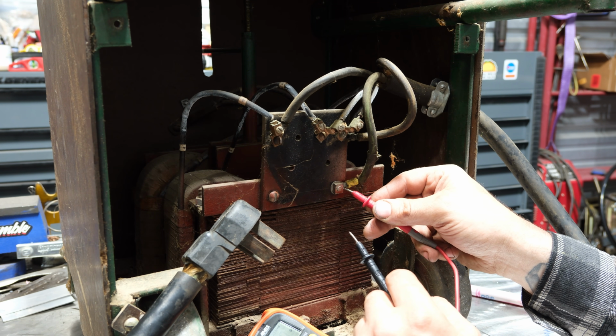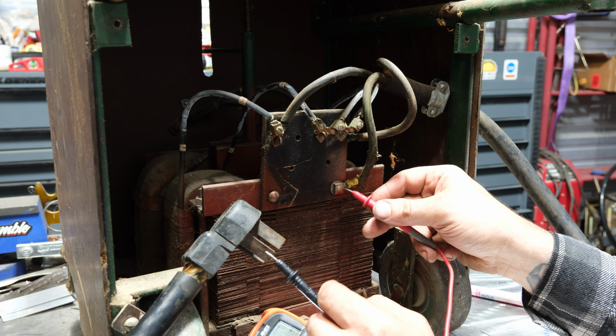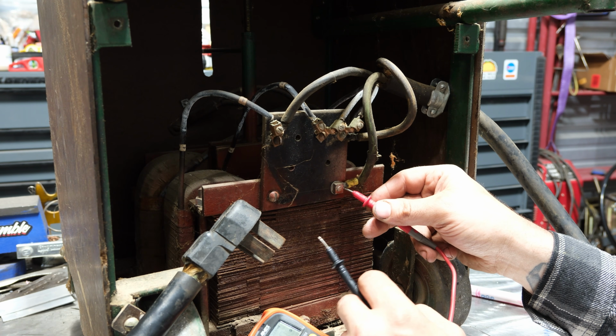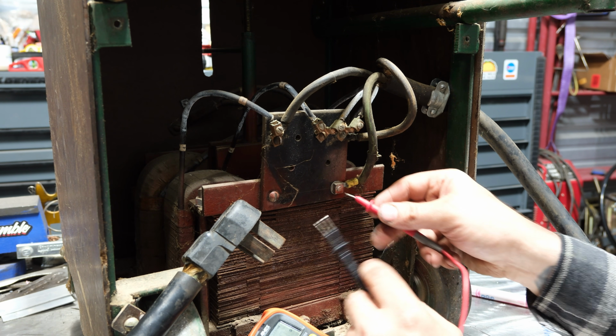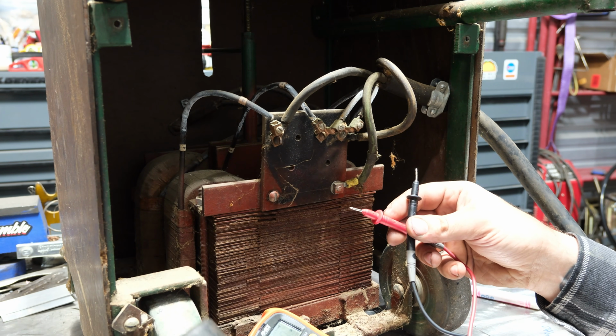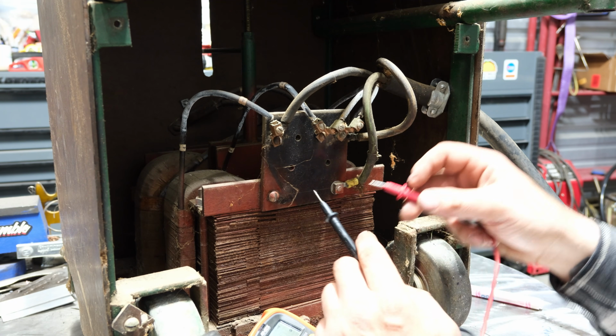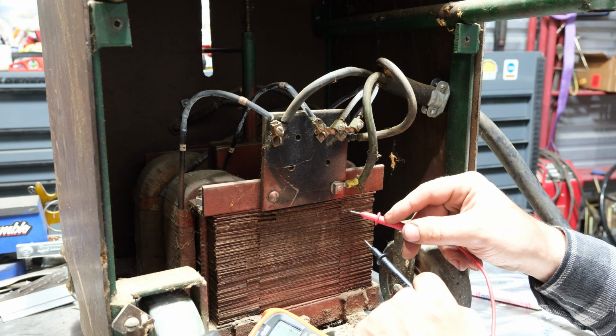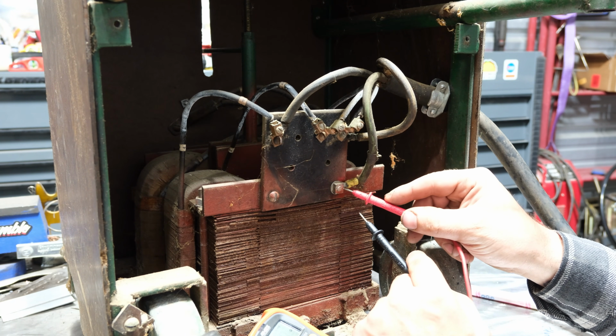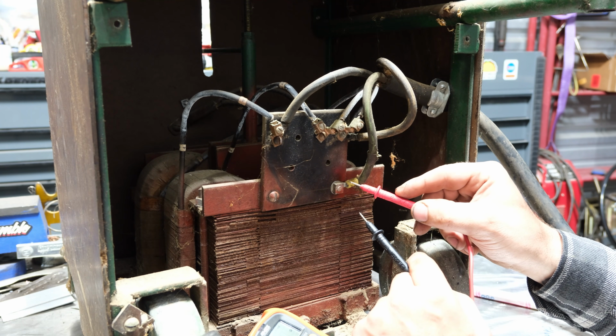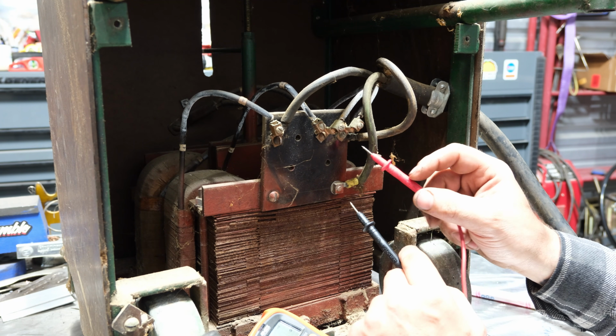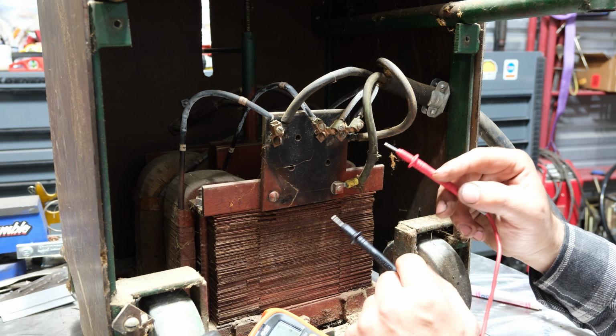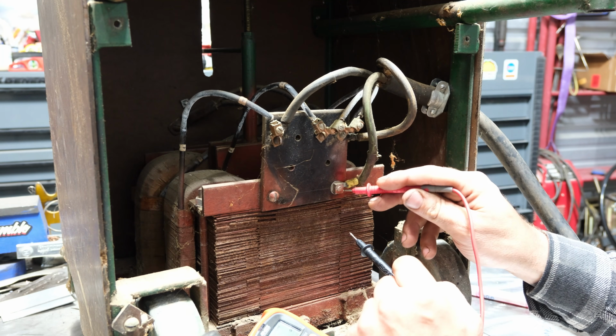That's a good sign. That's giving an indication that at least neither one of these inside of the cord is shorted to the ground wire, and the ground is indeed hooked up to the right terminal, which also means that it is wired correctly. Now, the main thing that I'm concerned with in here is that this ground wire is not actually hooked in any manner to either of the hot wires that are on here. And I'm going to show you here.